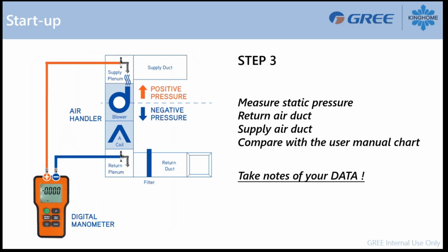Also, because the static pressure is really important, we have to take it below the coil in the return section. So if you have a base installed below your air handler, you can drill some holes inside this base and take your static pressure over here. If you want, you can pierce 3 different holes and make an average of all your return section. Same thing on the supply duct. Make sure you drill a hole here and take the static pressure reading of the entire air handler right here.